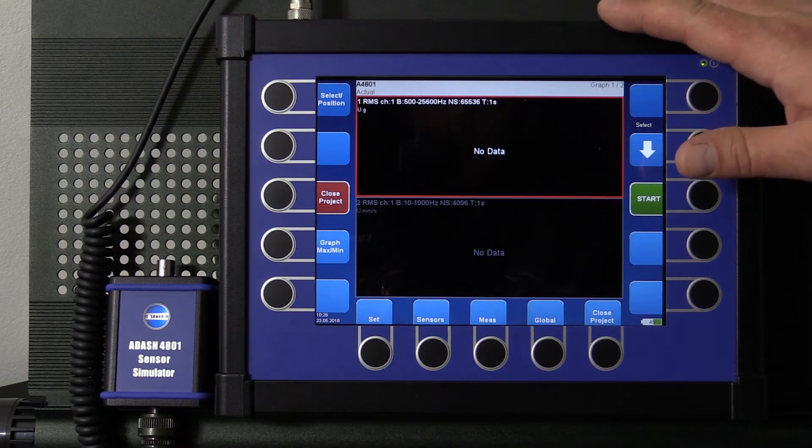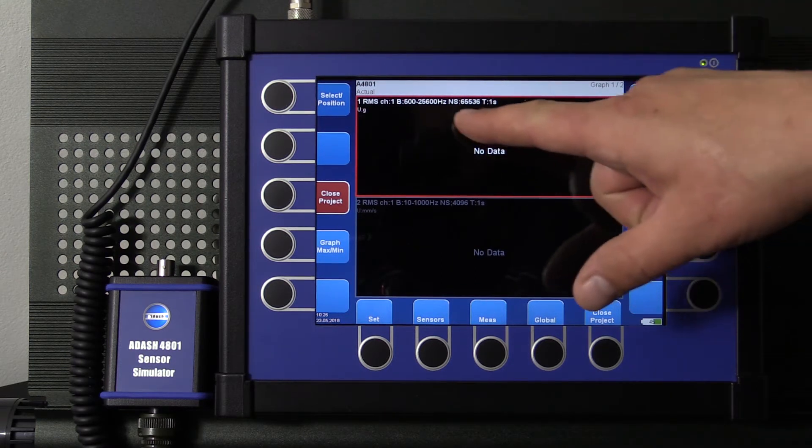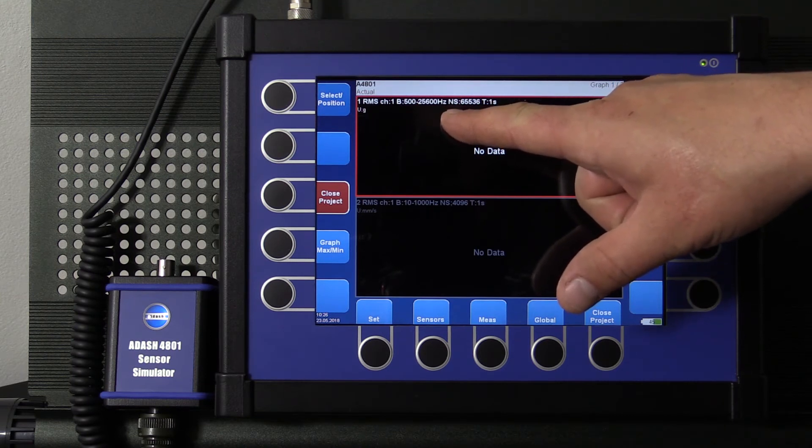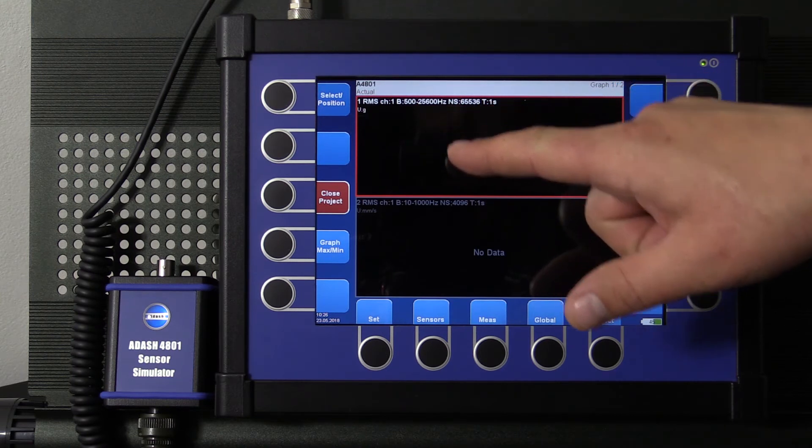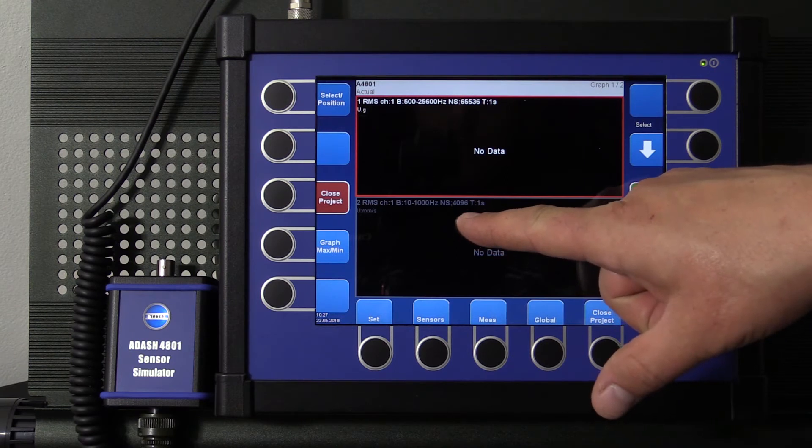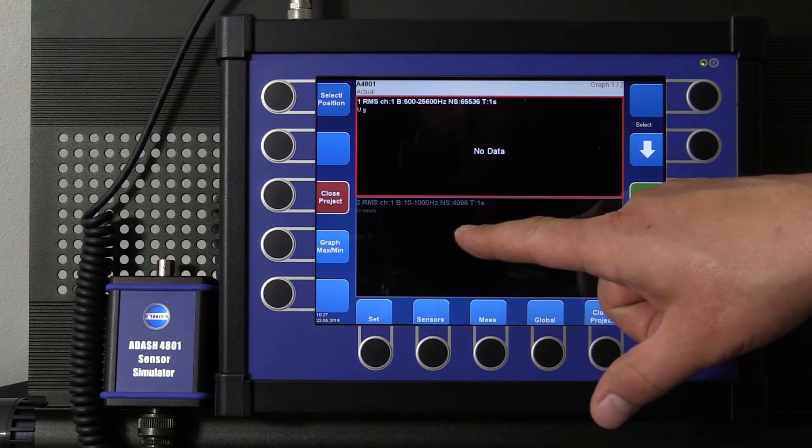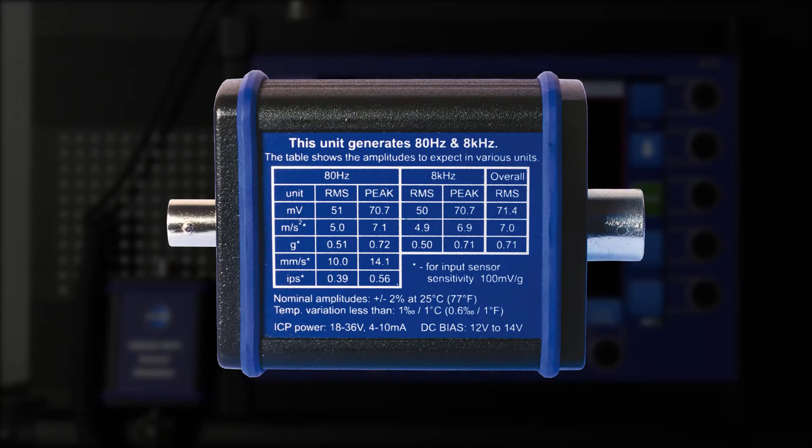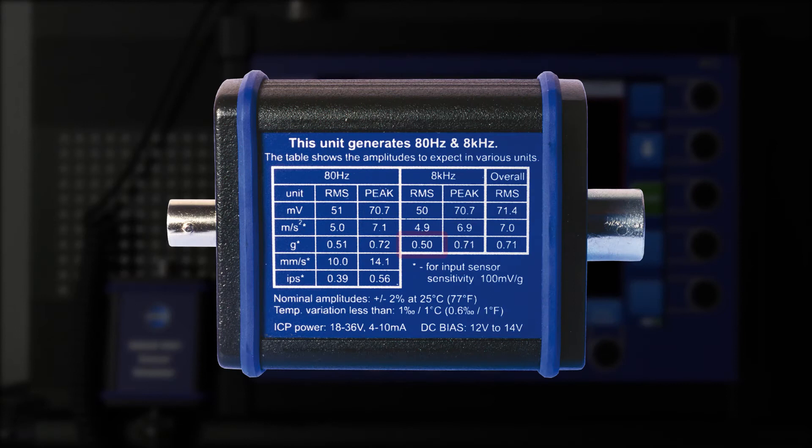Acceleration in G RMS in 500 to 25 kHz frequency range in order to have signal on 8 kHz. And velocity in mm per second RMS in 10 to 1000 Hz frequency range in order to have signal on 80 Hz. So we should see 0.5 G's in acceleration and 10 mm per second in velocity.